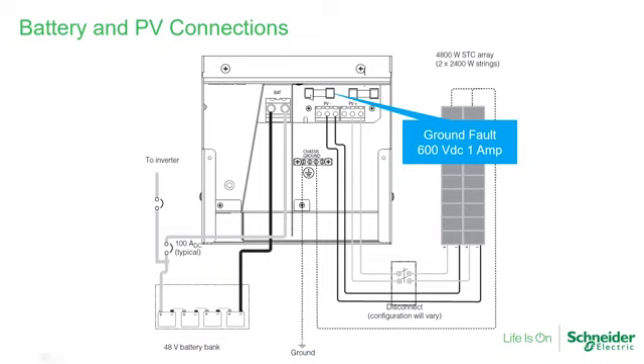The next thing is the ground fault. This product comes with a ground fault built in. When you receive it and open the box, you're going to find these fuses already installed here: a fuse on the positive and, sorry, this will be the negative side, and you need to remove one or the other. We can't have them both. It's simply that we don't know which one you're going to use. So remove the one that you're not going to use, and save it in case you ever have to replace the fuse.